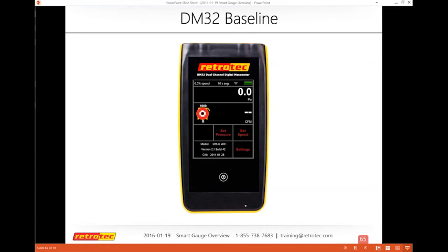Some options you can do if you have a high number fluctuating already is you can actually move that reference tube. The red reference tube can be moved anywhere outside. Jay's got a method that he uses where he puts it in another container. Some people bury it, some people put it in a tennis ball. As long as it has the ability to get atmospheric pressure and is not something that's closed off, like a bottle that can create a wind across it that creates pressures.